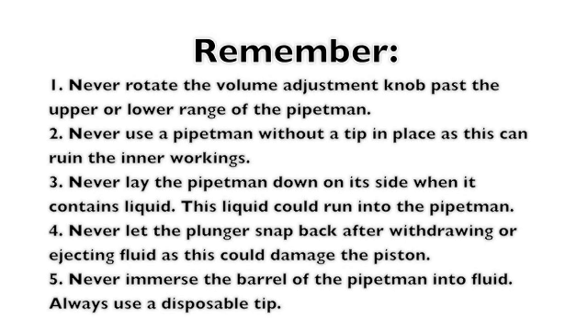Remember: never rotate the volume adjustment knob past the upper or lower range of the pipetman, as this will damage the pipette. Never use the pipetman without a tip in place, as this can ruin the inner workings. Never lay the pipetman down on its side when it contains liquid, as this liquid could run into the pipetman rendering it useless. Never let the plunger snap back after withdrawing or ejecting fluid, as this can damage the piston. Never immerse the barrel of the pipetman into the fluid. Always use a disposable tip.